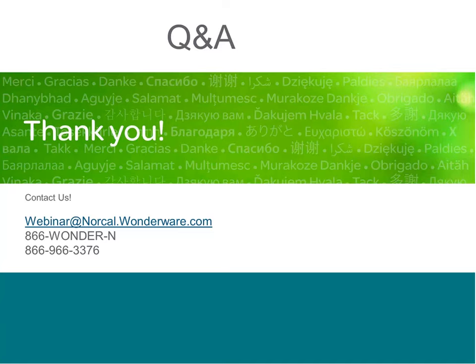Can you monitor historian tags within System Platform? If so, what is the resulting reference? Yeah, you can monitor. So if you want to look at the history summary data type that I was talking about earlier, that's one way, if you're using System Platform, to view the value in the historian. So you can look at the first value or the last value in the time period that you define, as well as any of those aggregated statistical functions. So that would be the preferred way.